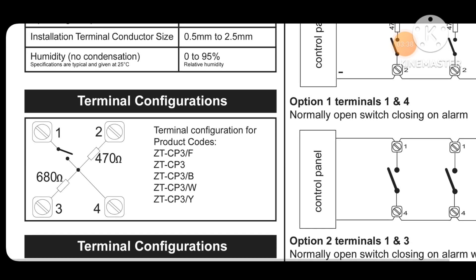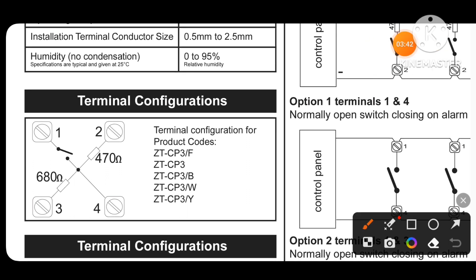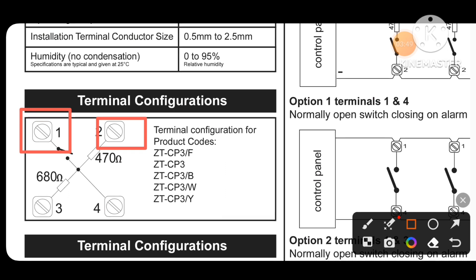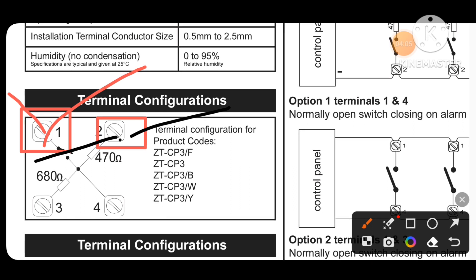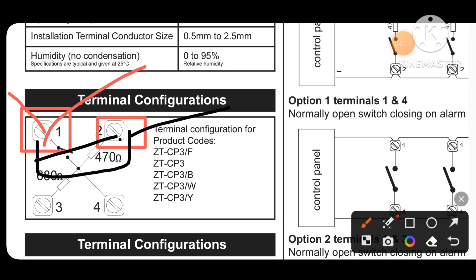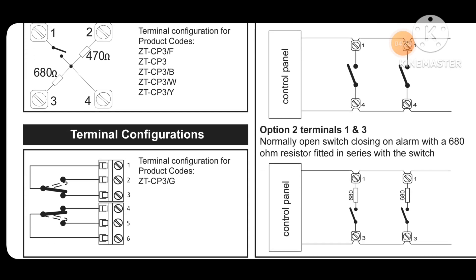Like this you can go on to the next devices. Generally we put termination on terminals 1 and 2 — one cable is coming in and going out, the other cable is also coming in and going out. If it is the last device, we can put our end-of-line resistor here. By this way we can easily connect our ZTCP3.